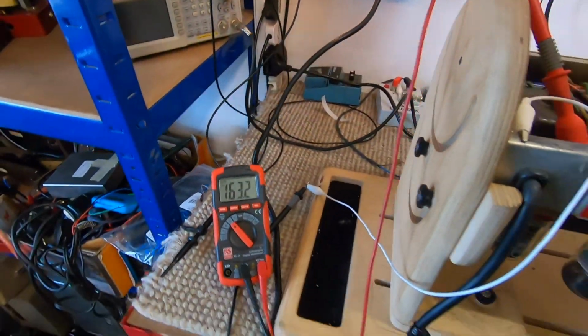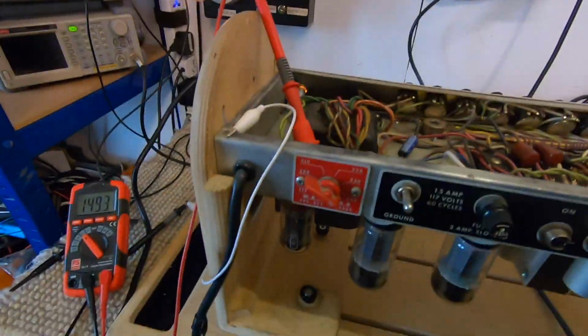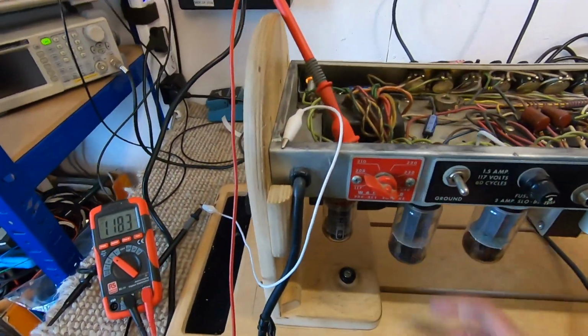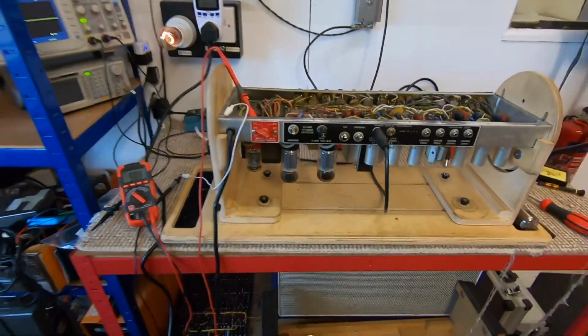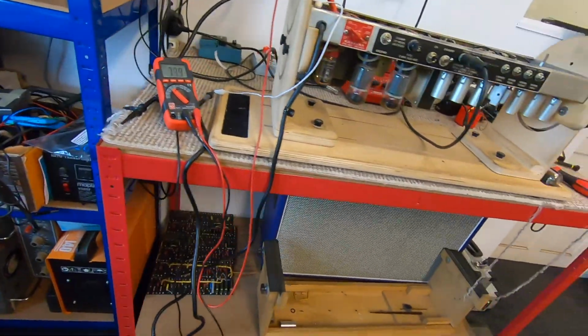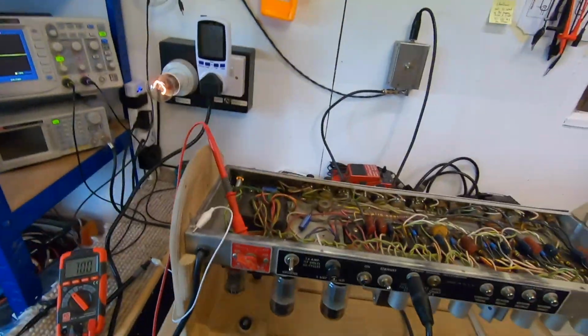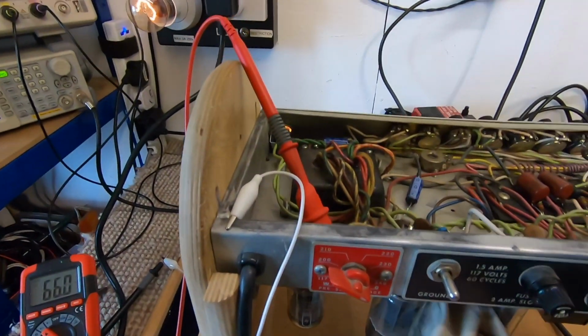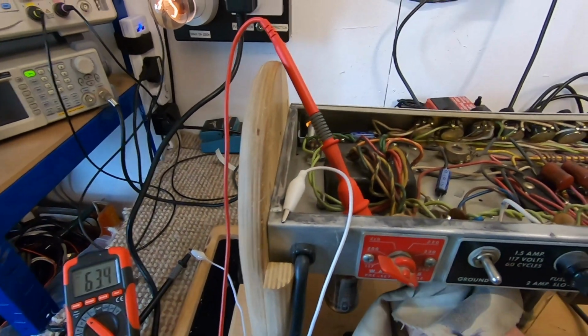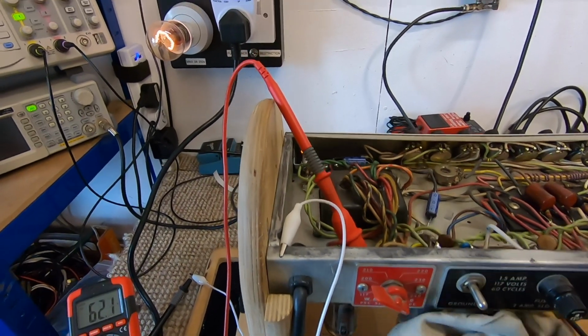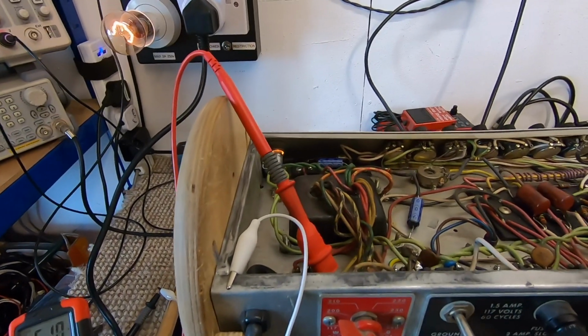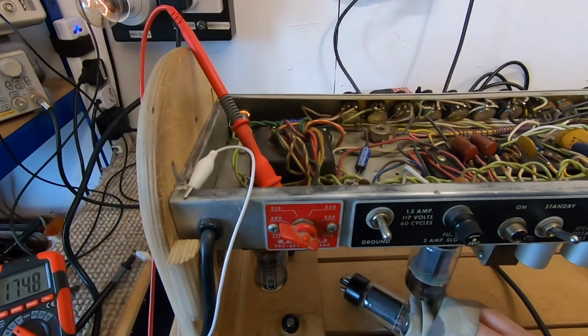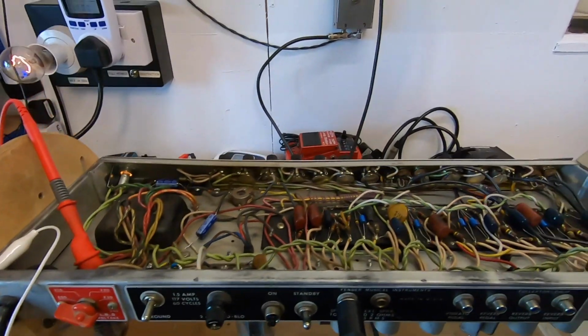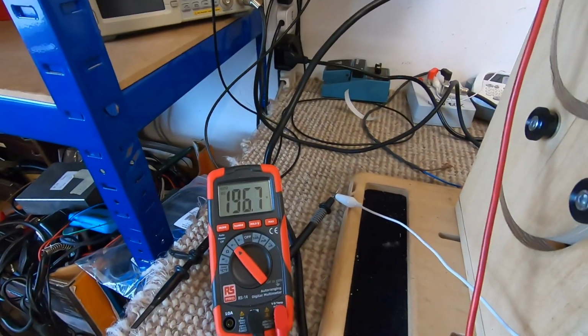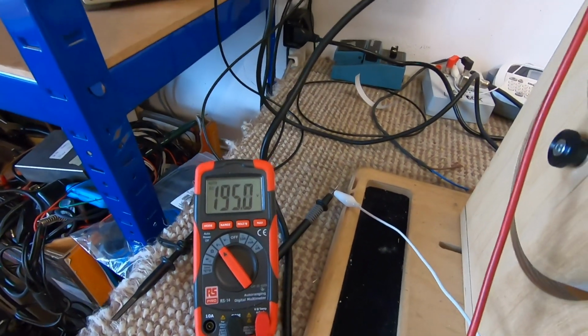So how do we find it? Keep it in restriction mode, and we're just going to pull the output valves at first, see if that helps us identify where our short is, or at least where in the circuit the fault may lie. See, now I've pulled that output valve, that voltage has jumped up again.